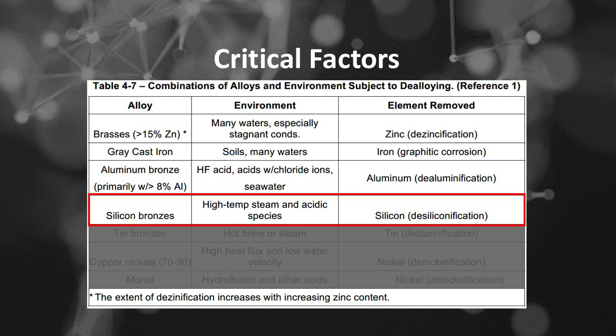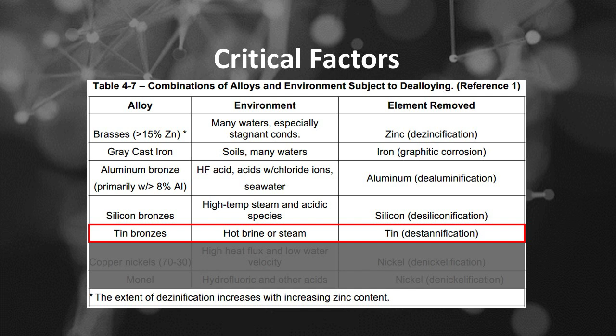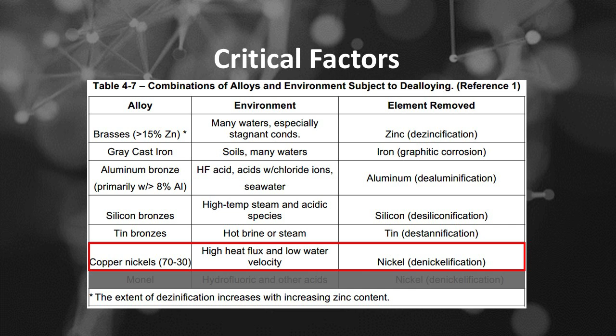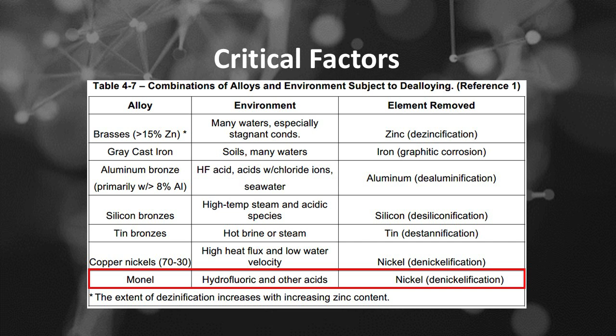If alloy is silicon bronzes, and if environment is high temp steam and acidic species, then element removed is silicon or desiliconification. If alloy is tin bronzes, and if environment is hot brine or steam, then element removed is tin or destannification. If alloy is copper nickels, about 70 and 30, and if environment is high heat flux and low water velocity, then element removed is nickel or denickelification. If alloy is monel, and if environment is hydrofluoric and other acids, then element removed is nickel or denickelification.